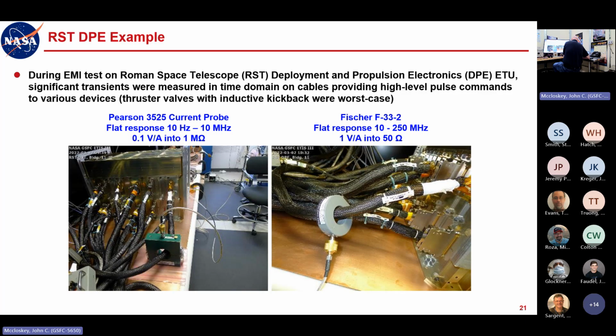If you don't know the characteristics going in, then I like to use these two different probes. Going down to 10 hertz, that's pretty darn close to DC, so the Pearson is going to tell me anything in the low frequency range, and then the Fischer is going to get me from... That's actually not totally accurate. The flat response is actually from a couple hundred kilohertz, like 300 or 400 kilohertz, and up. I must have just thought of it picking up at 10 megahertz. But the Fischer probe has flat response down to a couple hundred kilohertz. So there's some overlap in the ranges where these two probes have flat response.